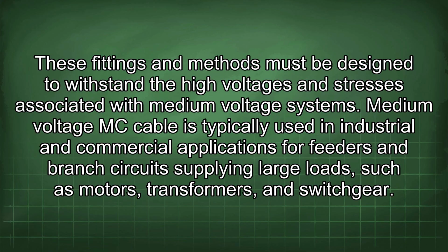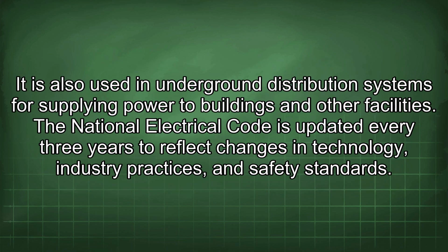Medium voltage MC cable is typically used in industrial and commercial applications for feeders and branch circuits supplying large loads such as motors, transformers, and switchgear. It is also used in underground distribution systems for supplying power to buildings and other facilities.